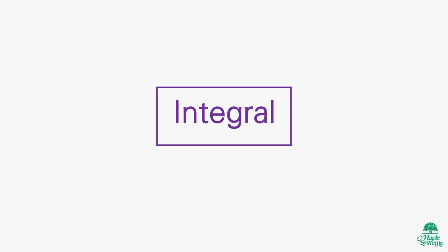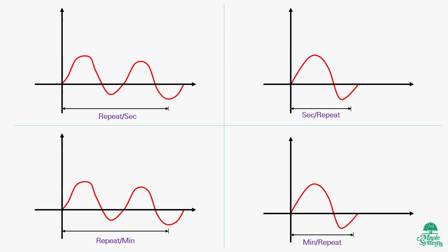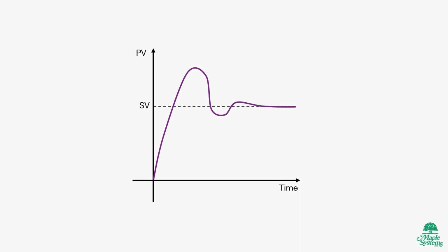The I in PID stands for integral, often called reset. This parameter is also called KI or TI. It determines how fast the steady state error is removed. Adjusting the integral properly will result in less oscillation when headed towards the set value. The integral control or reset is based on the time it takes to reach a target value or set value. It cuts down the error from the proportional gain, so it tries to eliminate any deviation.